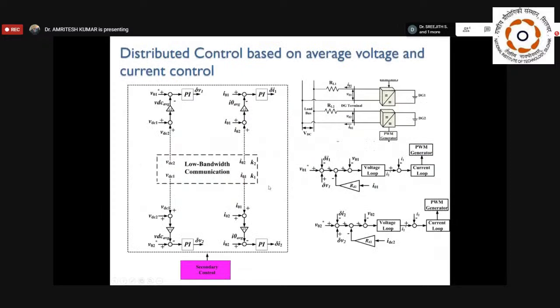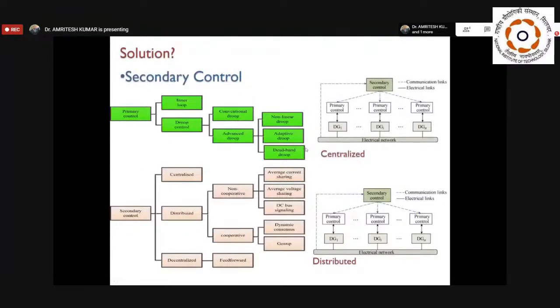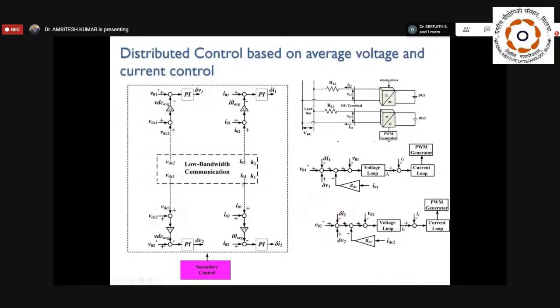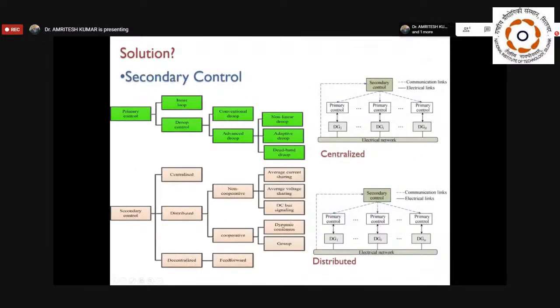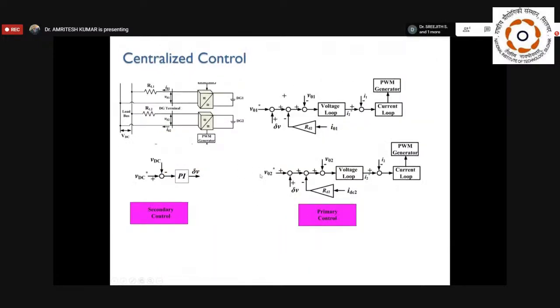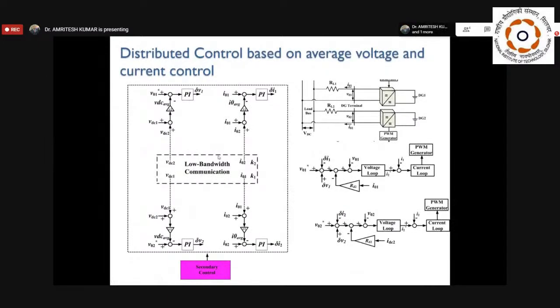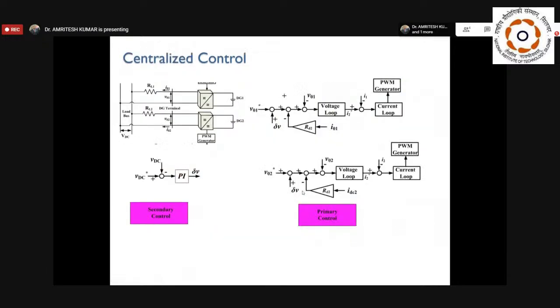So what is the conclusion? Basically, this distributed control enhances the operation of your average control based on average voltage and average current. If you see the research part, I have just covered average voltage and average current, but you will find there are different methods nowadays being used to enhance the performance. You will find some control that is based on average droop resistance also, how to adapt the droop from the secondary control itself. So it is going to have the information of the droop of all the converters. Accordingly, it will give the optimum value of droop to be applied for the control of the converters. So basically, this distributed control enhances the performance.